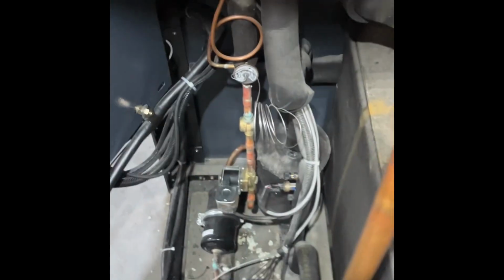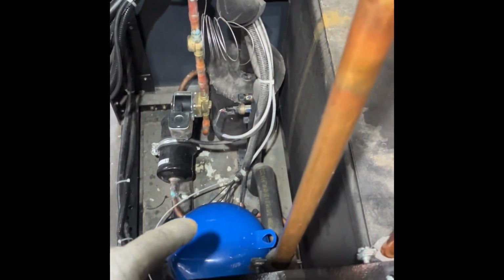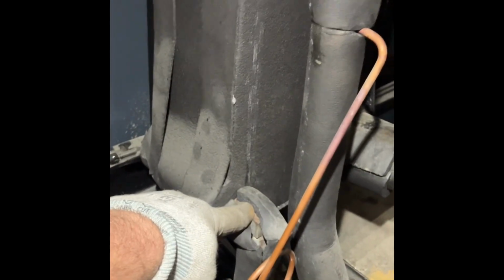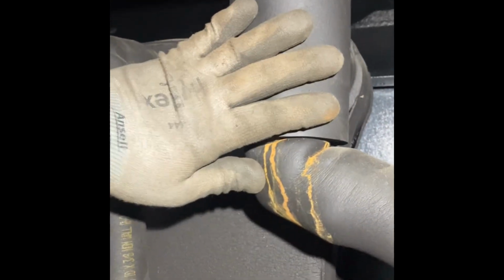So for those of you unfamiliar with how a Zeks dryer works, just like any refrigerated dryer, you have your refrigeration system down here. But the way that these things exchange heat is a little different. And so right here, we have the refrigerant to glycol heat exchanger. You can see we've got our line coming in, runs through the heat exchanger. Then this is our suction line that runs down through the accumulator, ends up back to the compressor. And then on the other side of this heat exchanger, you have your glycol inlet and your glycol return.